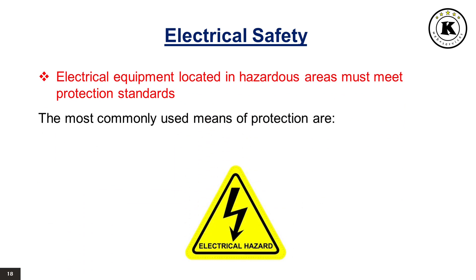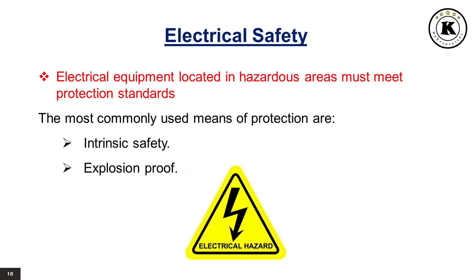Electrical safety: Electrical equipment located in hazardous areas must meet protection standards. The most commonly used means of protection are: Intrinsic Safety — a protection technique for safe operation of electrical equipment in hazardous areas by limiting the energy, electrical and thermal, available for ignition; and Explosion Proof — meaning the enclosure must be able to internally withstand any internal explosion and any sparks generated internally, preventing these sparks from igniting any vapors, gases, fibers, or dust in the surrounding environment.